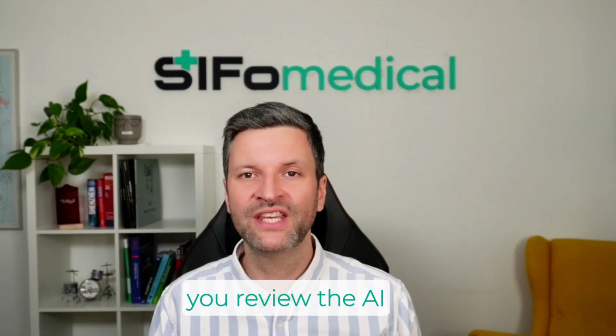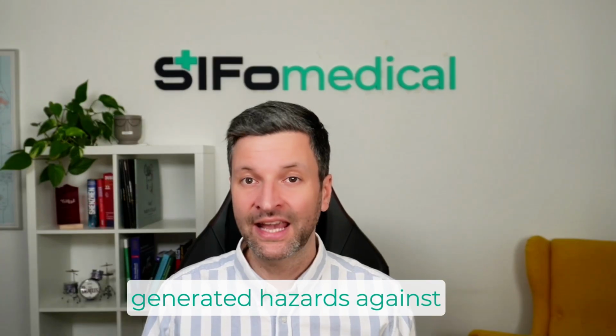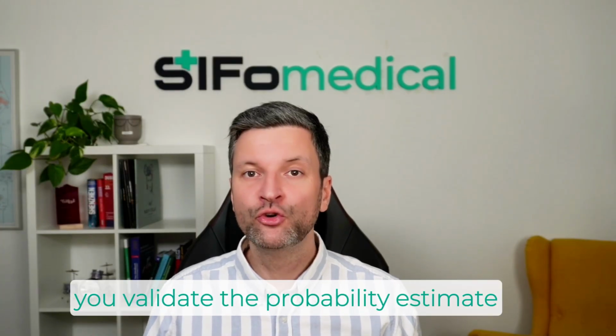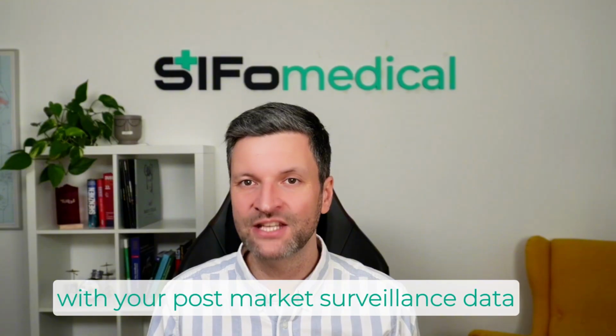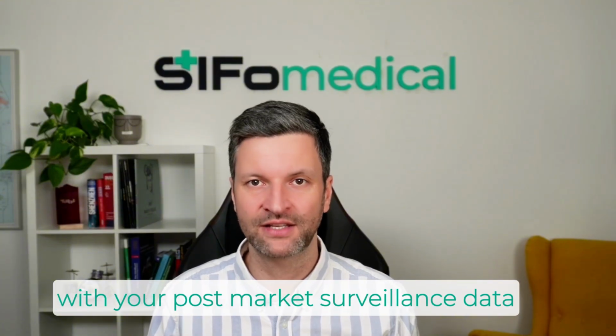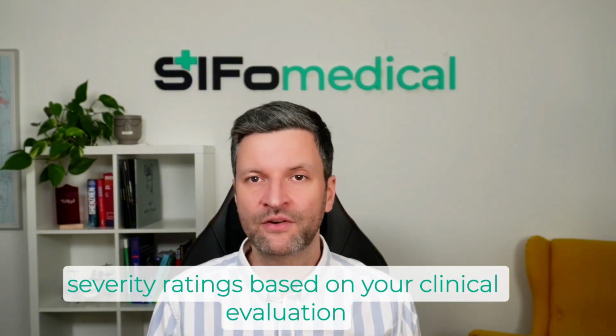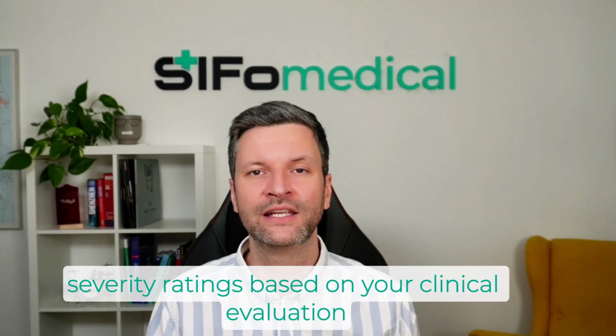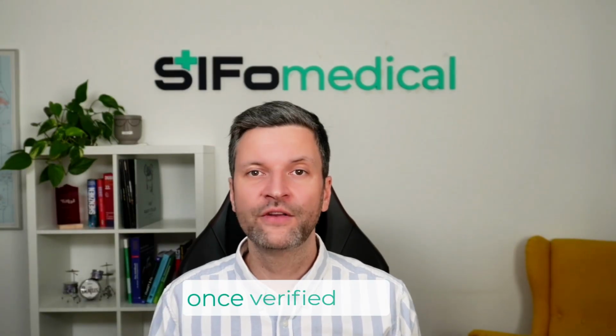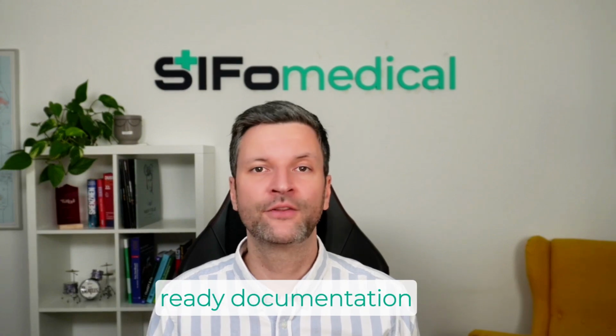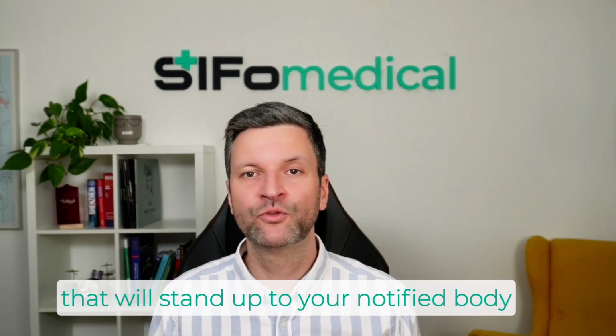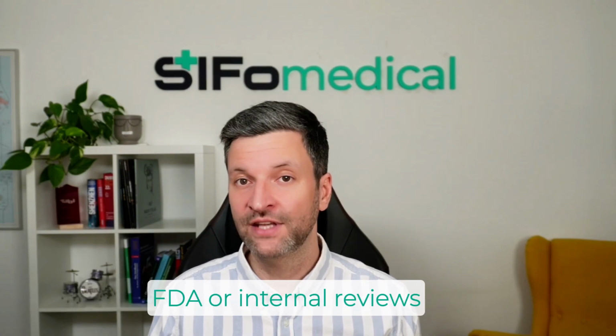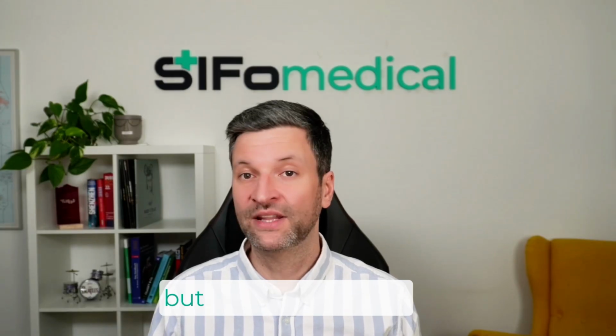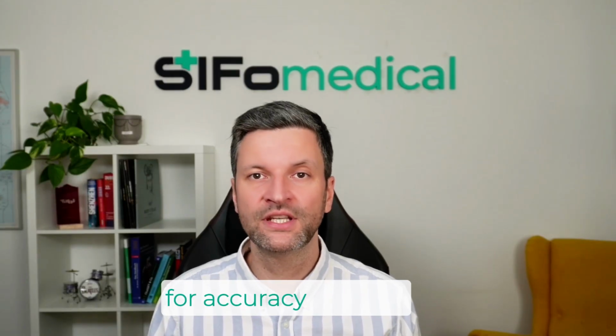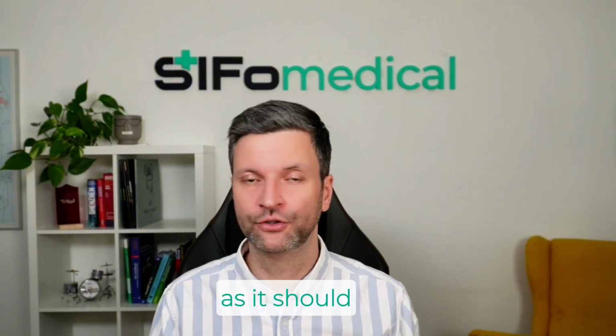You review the AI-generated hazards against your documentation. You validate the probability estimate with your post-market surveillance data. You confirm severity ratings based on your clinical evaluation. Once verified, you have audit-ready documentation that will stand up to your notified body, FDA or internal reviews. But the responsibility for accuracy remains with you, as it should.